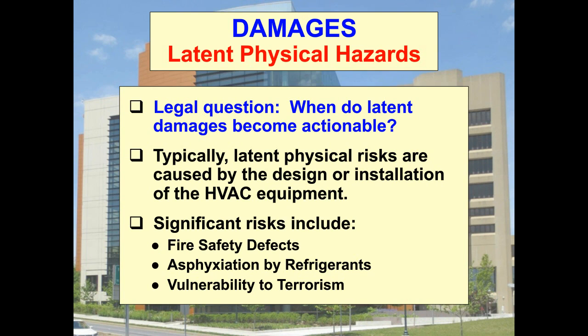Another case involves so-called active fire protection systems that control HVAC fans to clear out smoke during a fire. These schemes are vulnerable to failure, as was demonstrated recently in the Washington, D.C. subway, where ventilation fans were operated incorrectly, resulting in the deaths of passengers on a stalled train. That was about a month or two ago.